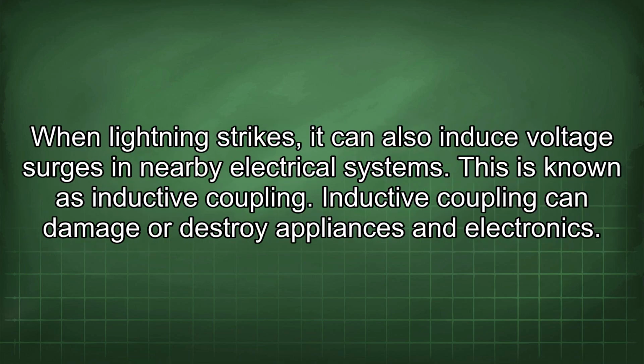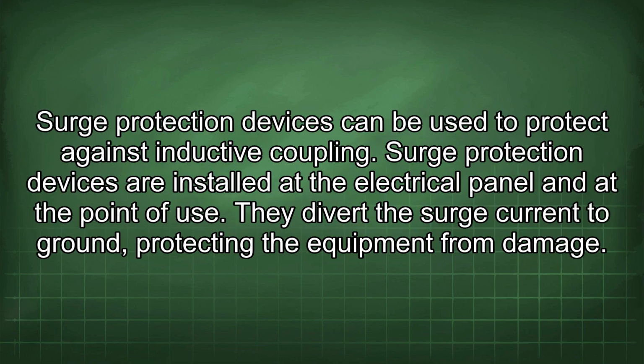When lightning strikes, it can also induce voltage surges in nearby electrical systems. This is known as inductive coupling. Inductive coupling can damage or destroy appliances and electronics. Surge protection devices can be used to protect against inductive coupling. Surge protection devices are installed at the electrical panel and at the point of use. They divert the surge current to ground, protecting the equipment from damage.